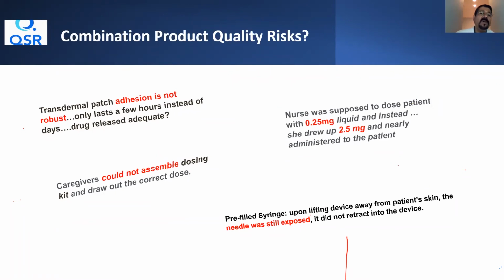Caregivers could not assemble the dosing kit and draw out the correct dose. Very simple. These are the nurses or anybody who are the caregivers; the way they should assemble the kit, and then the dose, they are not able to do. These are all the user risks you need to identify and mitigate. Prefilled syringes: upon lifting the device away from the patient's skin, the needle was still exposed, which is supposed to be retracted. So it's the prefilled syringes or the auto injectors. If the needle did not retract into the device, then it is a design issue.